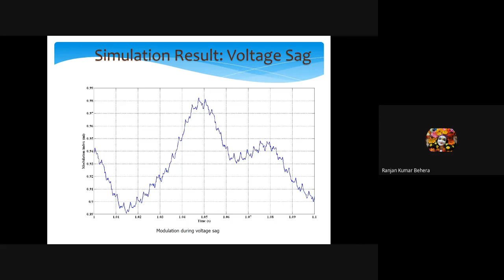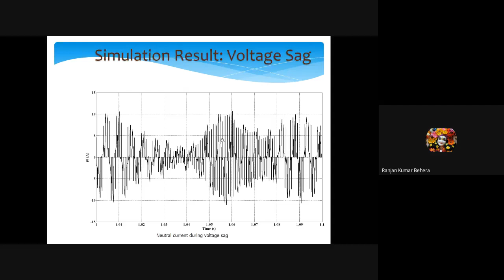So as you can see, they try to maintain the output voltage. That is why the government is asking the companies that the turbine should be connected to the grid during the fault condition also. That means if it is connected there, what you need to do is only change the controller structure. During that period the controller must give this, and this is why the modulation index rises. Now here you can see the neutral current: during the voltage sag there is neutral current, and during the normal time there is low current in the neutral.